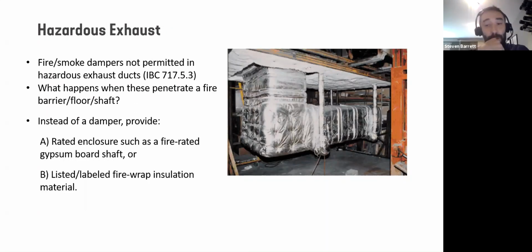Now, there's, of course, a lot of special cases. One fairly common one: I said you have to provide fire dampers in all these locations, and fire and smoke dampers, but we're not permitted to do that in hazardous exhaust. So what do we do? In those cases, your options are to either provide a shaft, a rated enclosure to protect the ductwork all the way to the roof or exterior, or provide a listed and labeled fire wrap for that system.